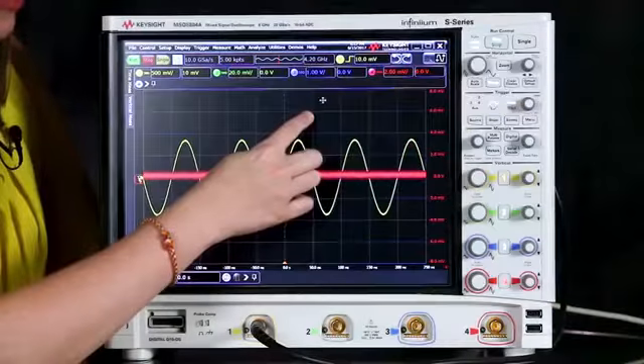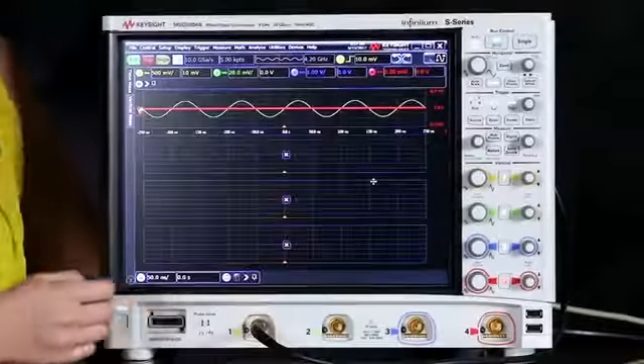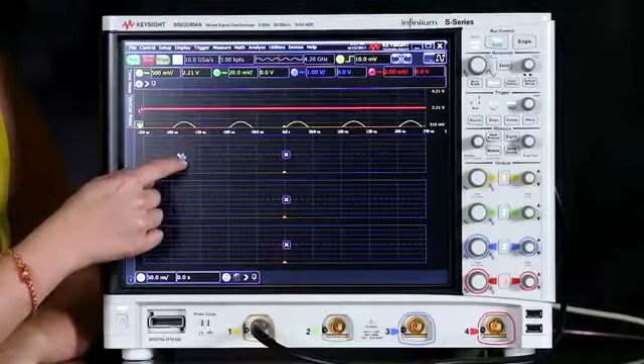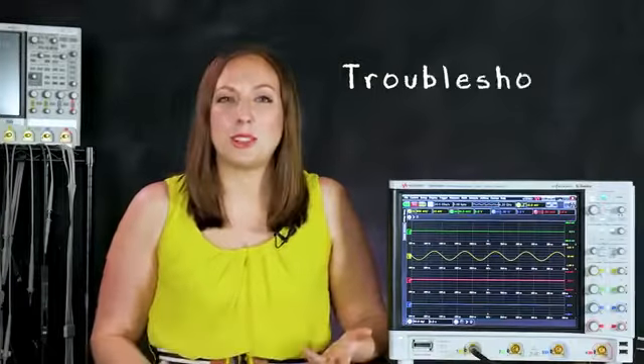We can also view these waveforms separately in their own grids. So we'll right-click and then we'll choose number of grids and we'll select four. And we can drag and drop each of the waveforms to its own separate grid. Now we're ready for viewing our waveforms and doing basic troubleshooting.